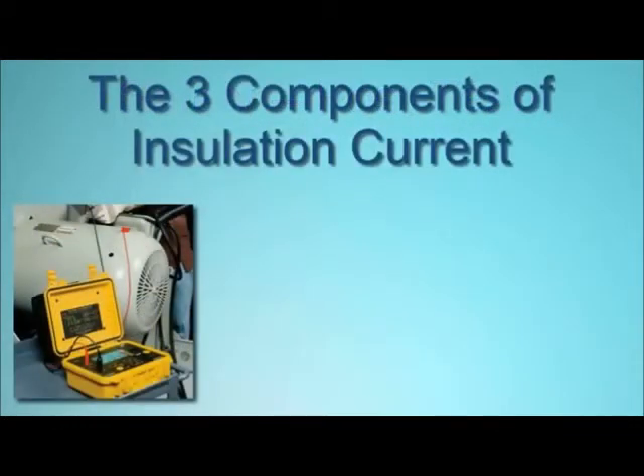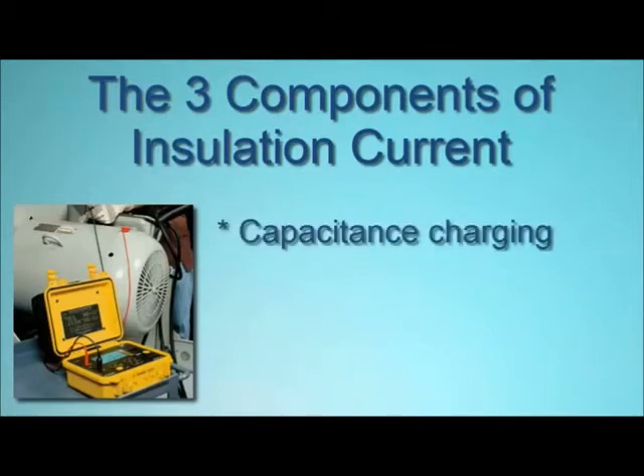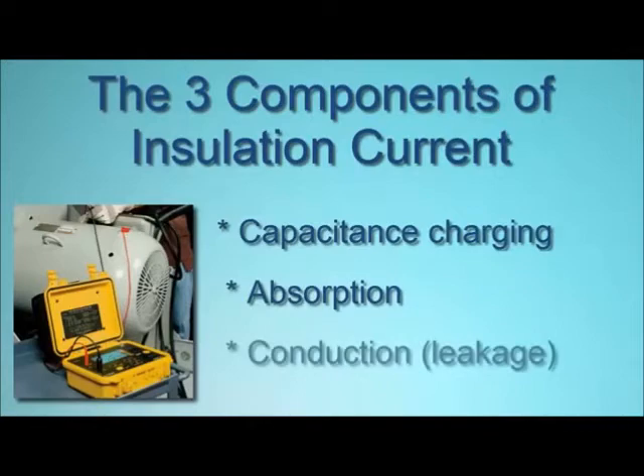To properly interpret test results, it's important to understand that the total current flowing through the insulation consists of three components: capacitive charging current, absorption current, and conduction or leakage current.